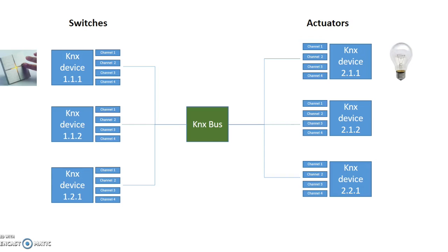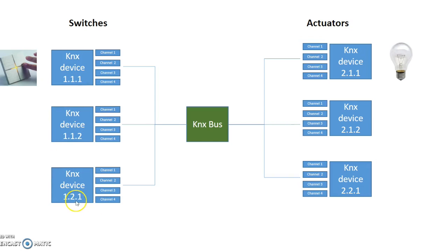In essence, the KNX system is a series of devices that are connected through a communication bus to one another. These devices are often categorized as either switches or actuators. Switches can be things like a light switch, a movement presence detector, or a temperature measuring device. Each of these devices will have their own individual address, and those addresses will be different from one another, meaning each individual device on the bus can be individually identified.